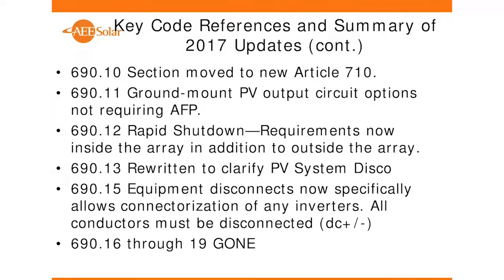So if it's either a plus fuse system or a minus fuse system, you can't have plus fuses on part of the array and minus fuses on another part of the same array. That's not allowed. That's a nightmare, and that's actually happened before, and it doesn't work real well.